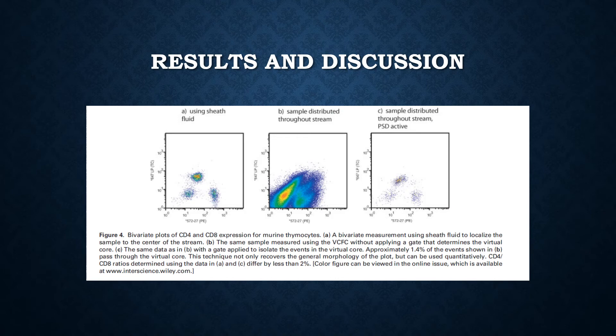We have two graphs: in B without the gate, and in C the gate is active, which eliminates the virtual core, or pretty much subtracting the virtual core from the graph, which gives you the pure results. In comparing A and C, using the sheath fluid versus using the VCFC, we can see almost the same results. According to the article, there is only less than two percent difference in numbers, which shows that the numbers are so close and there's no significant difference between the results.